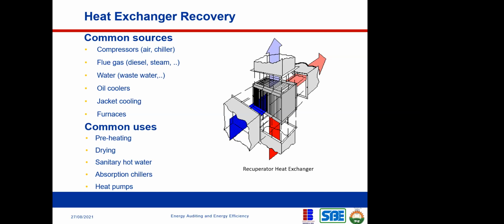So for industrial applications, if you have a large power plant, you can actually extract some of this heat from the oil, from the plants, and then use it either to preheat water, right? Or if there are places where you need low-grade heat, you can actually use it for those kinds of processes. Okay. This oil cooler is similar to the jacket cooling that I just explained about generators, when you have to pour oil to lubricate and they get hot and all of that. Okay. So your furnaces, okay, your furnaces are also a source of heat that you can recover. So common uses of this kind of heat, you can do preheating, you can do drying, you can do sanitary hot water where you need low-grade heat, you can do absorption chiller, you can do heat pump. We're going to talk about heat pump and some of these technologies as we continue.